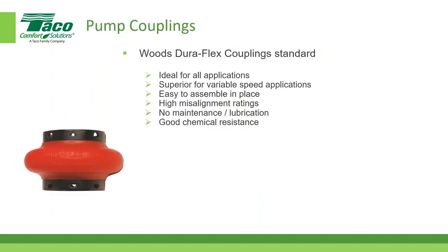The pump couplings are Woods Duraflex. Couplings are standard. They're ideal for all applications. Superior for variable speed applications. So we standardized on those quite a long time ago. Just keep that in mind. This coupling has two halves. When you take it apart, right, you'll see the two couplings of the two shafts lining up against each other.